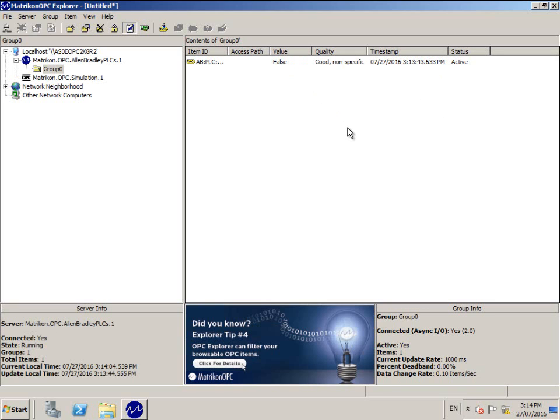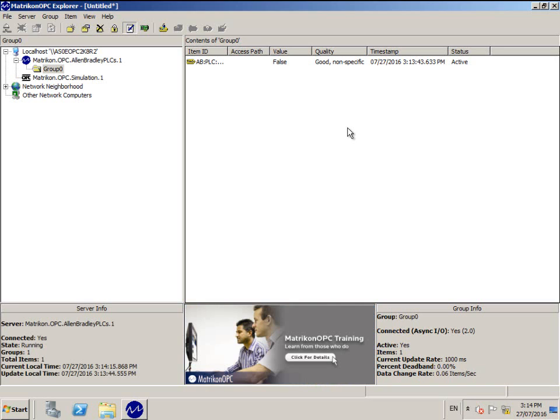Just remember that any time you change the program in the PLC, you must open the OPC server configuration and tick the Reread Configuration from PLC box and click Apply. You may also have to disconnect and reconnect your OPC client to update the browse list when this is done.